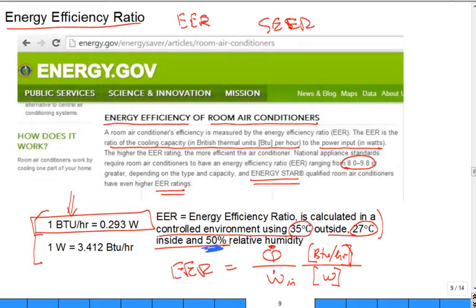That'll put a greater latent load on your air conditioning system — it's harder. If you have low relative humidity, it's actually easier. This is the air coming out to keep it at 27°C. This is your 35 degrees C outdoor air. Do they have a relative humidity on the outdoor air? Nope. You're rejecting it to outdoor air. You're worried about relative humidity because of the possibility you condense it on the evaporator coil.